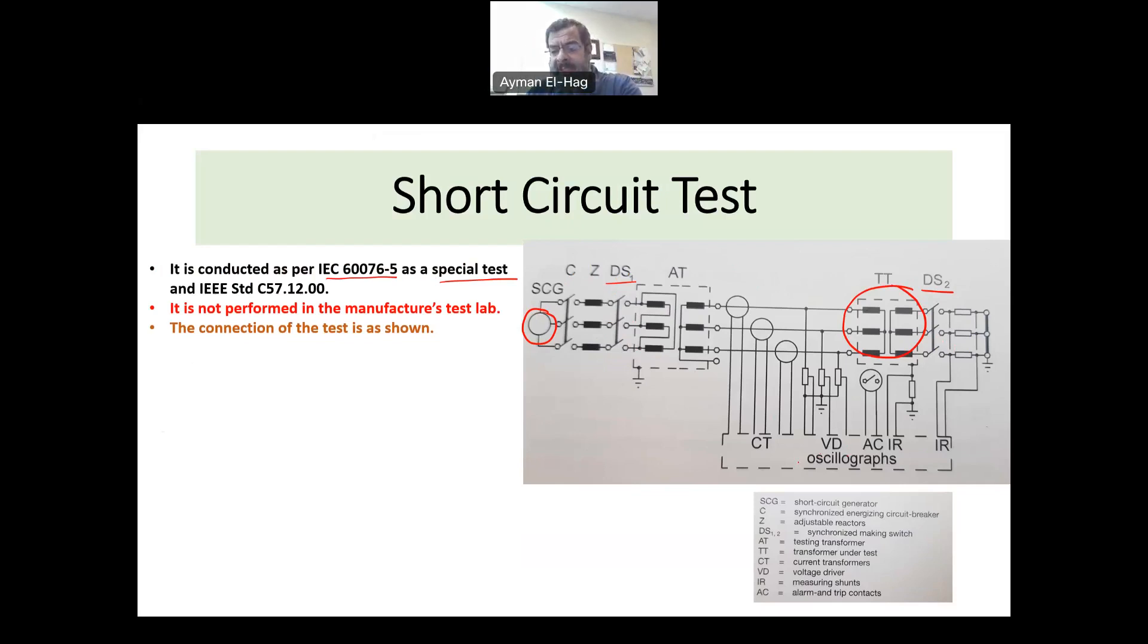Now, there are CTs and VTs to monitor the current and the voltage during the test. How is the test performed as per the IEC standard? You apply asymmetrical short circuits on each phase three times. So each phase will be subjected to a single line to ground fault three times, total of nine times for a three-phase transformer. As per the IEEE, you have two asymmetrical shots plus four symmetrical shots, total of six per phase.